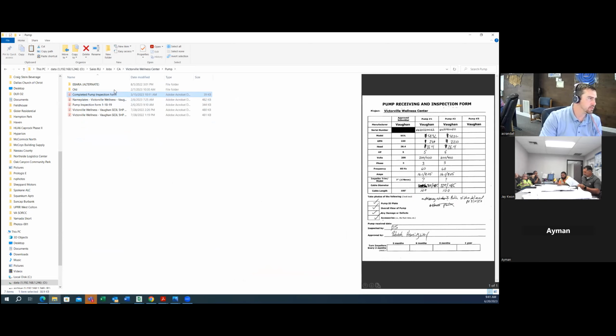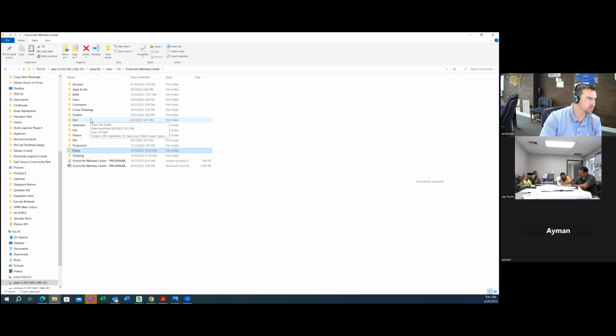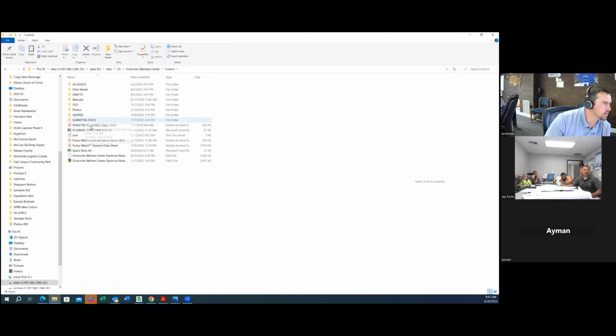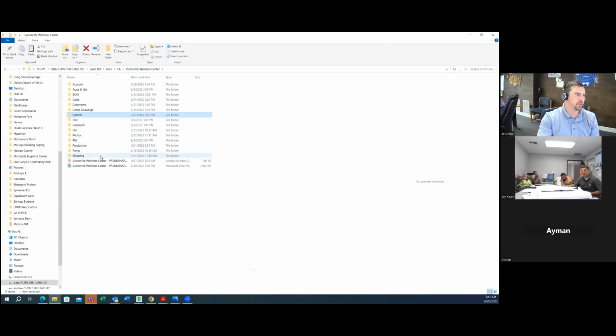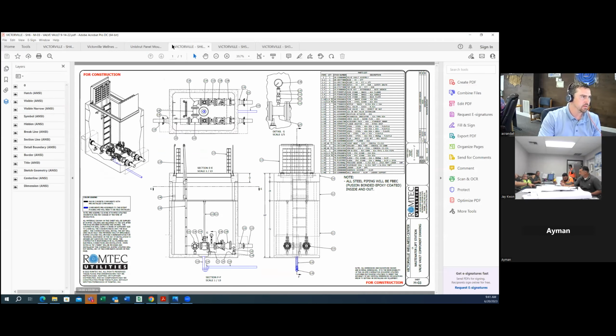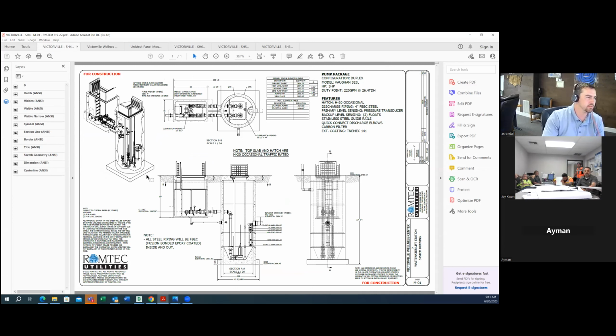Okay, perfect. The level sensing I think is probably a little shorter. Those are typically like, is it 60 meters? Let's see. 30 meters. So close to 100 feet. So, by the time you get down to 20 meters, so a little over 60 feet, by the time you get down, what's that? It's almost 20 feet. Let's just say you've got 20 feet of cable in the wet well by the time it turns off the hanger and gets into the conduit. And then whatever length of your conduit run is, and then the vertical run up into the control panel. You've got, we'll say, 80 feet of pump cable outside the wet well, and then probably 40 feet for level sensing.